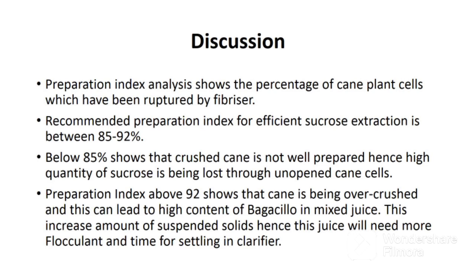The recommended preparation index for efficient sucrose extraction is between 85% and 92%. Below 85% shows that the crushed cane is not well prepared; hence, a high quantity of sucrose is being lost through unopened cane cells. In this case, the lab analyst should inform the mill engineer to stop milling and weld or replace the fibrizer tips.